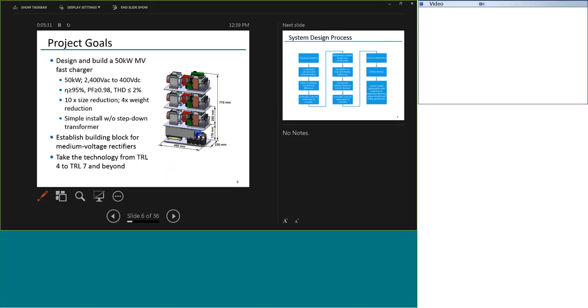So going on with our project goals, what we're trying to develop is a 50 kilowatt charger at this point, connecting directly to the medium voltage line. So the rating is 50 kilowatts connected to 2.4 kV, delivering 400 volts DC nominal to the vehicle. Efficiency over 95%, high power quality, 10x size reduction, and 4x weight reduction, with a simple installation without a step-down transformer. We're hoping this can help us establish a building block for medium voltage rectifiers, both through the lessons learned in building medium voltage rectifiers, but also since the system is modular, as I'll mention in a minute, we can scale to higher voltages and higher power levels. And finally, of course, our goal is to go from TRL4 to TRL7 and hopefully beyond.